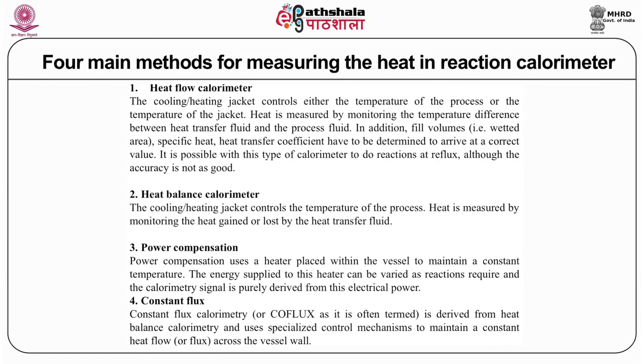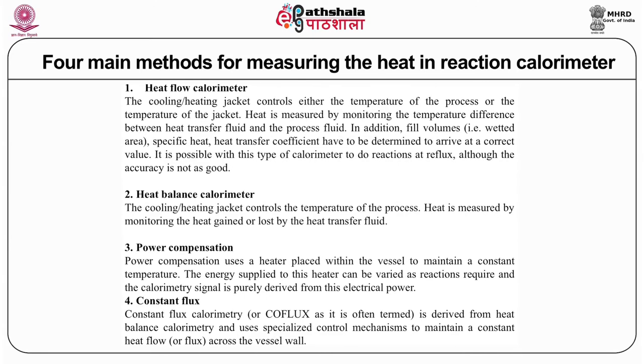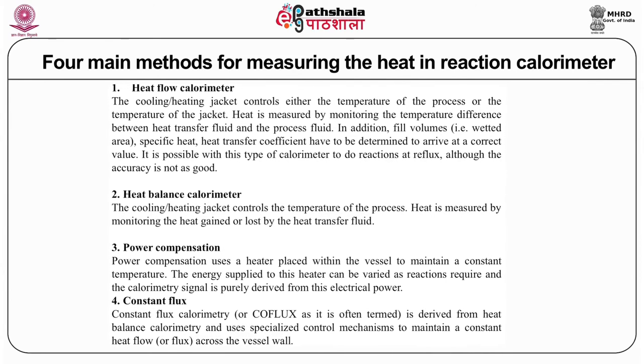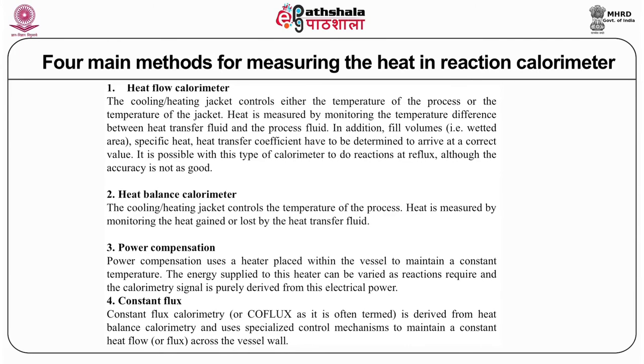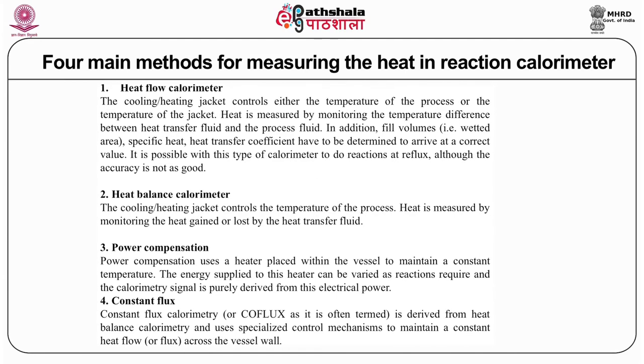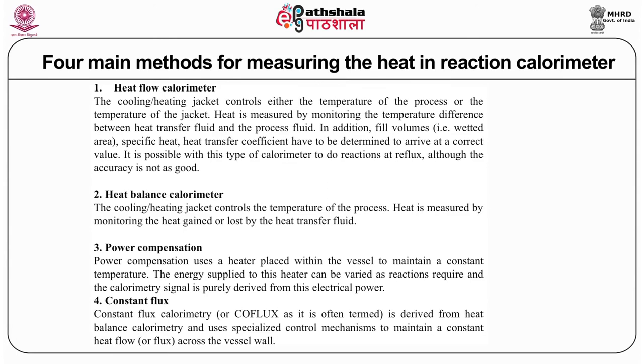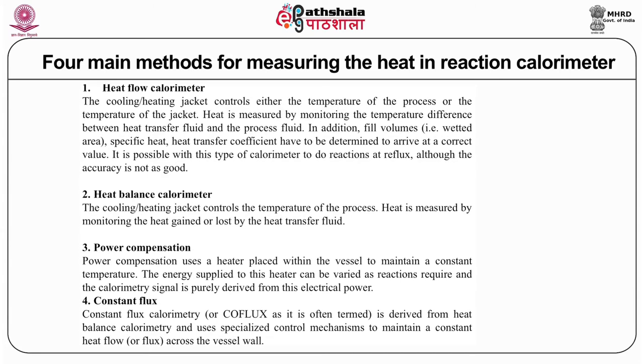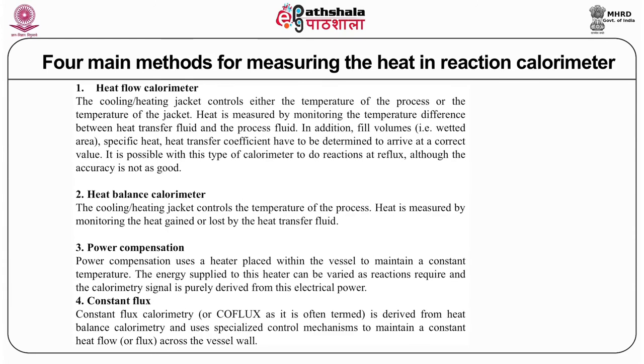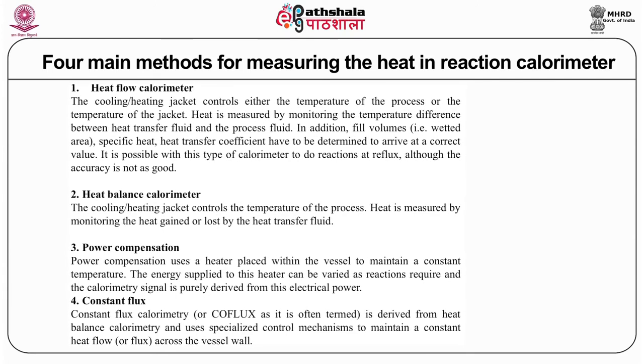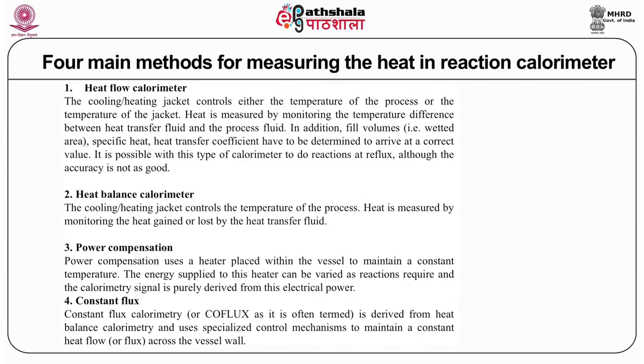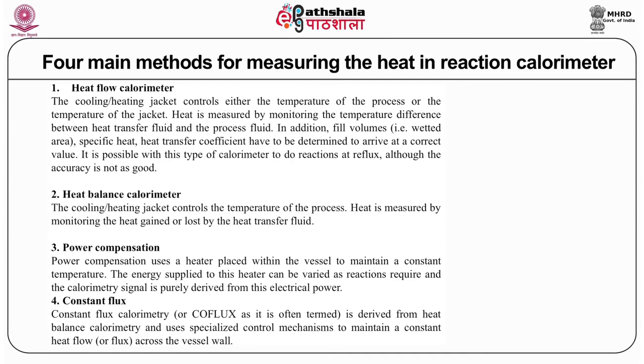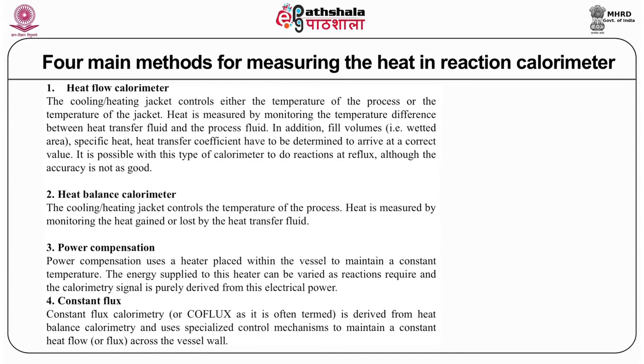The second type is the heat balance calorimeter, where cooling and heating jackets are controlled and heat is measured by monitoring the heat gained or lost by the transfer fluid. The third is power compensation, which uses a heater placed within the cell to maintain a constant temperature — a similar principle will also be used later in microcalorimetry. The energy supplied to the heater can be varied as required, compensating for the different amounts of energy released or absorbed by different reactions.